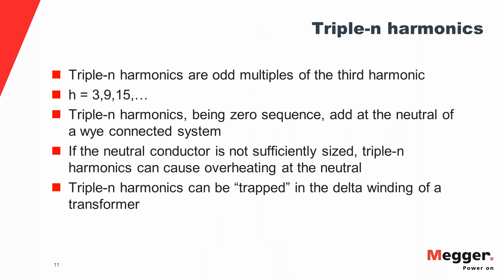Triple N harmonics are odd multiples of the third harmonic: third, ninth, fifteenth. Triple N harmonics are zero-sequence harmonics, though not all zero-sequence harmonics are triple N harmonics. Triple N harmonics, being zero-sequence, add at the neutral of a Y-connected system. Because they are zero-sequence on a three-phase system, the currents flowing through the A, B, and C phases have no phase angle difference between them — they are in phase. When they converge at the neutral, they add up, resulting in a large total current flowing through the neutral conductor.